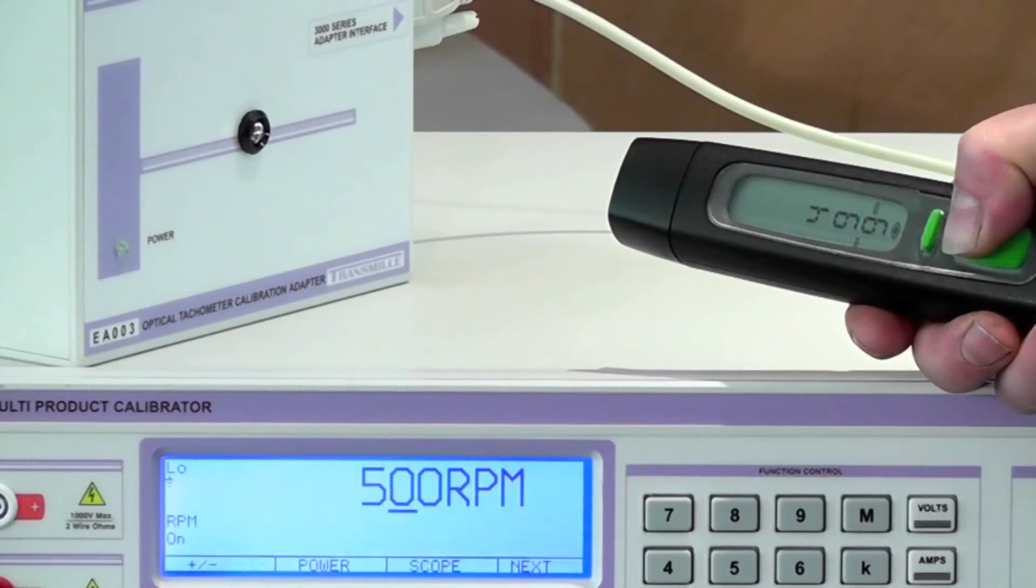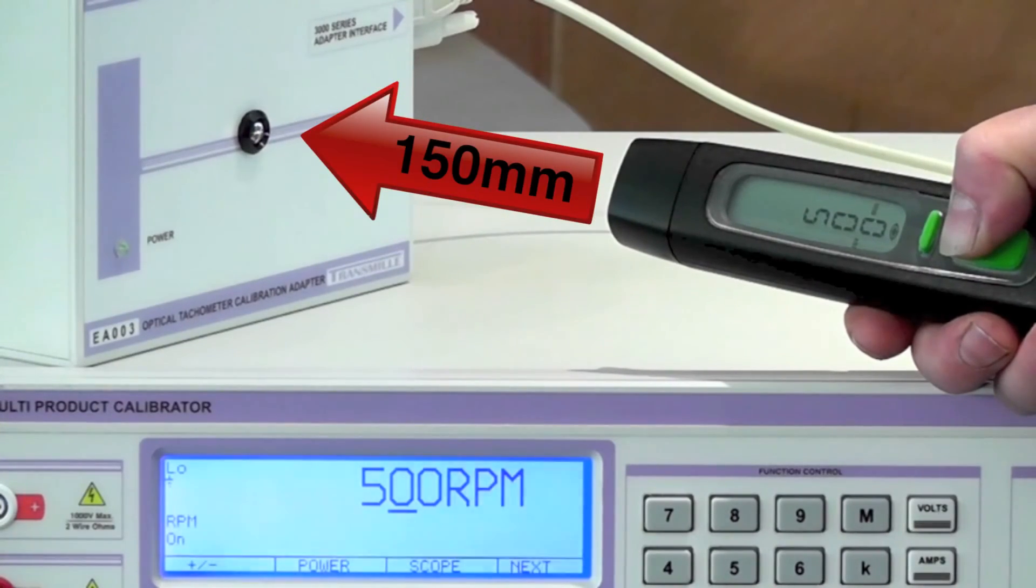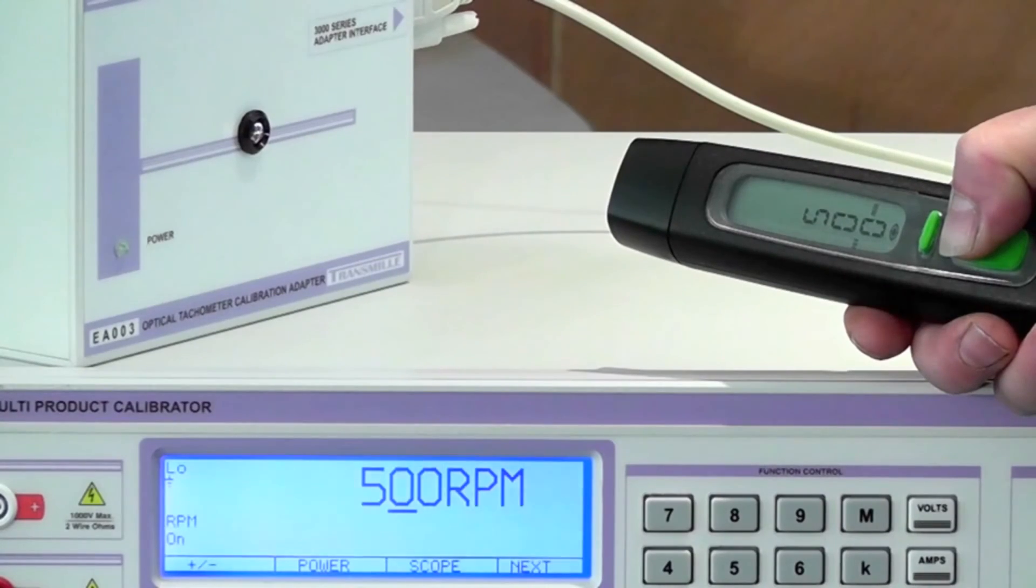To calibrate the optical tachometer under test, aim the device at the light source approximately 150 mm away from the adapter. To ensure correct placement, check that the device on target sign is displayed.